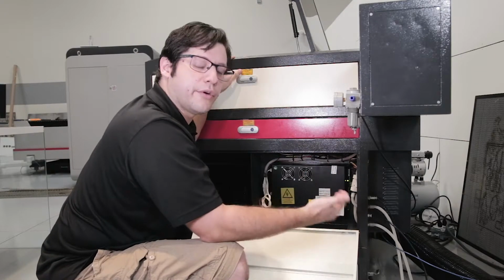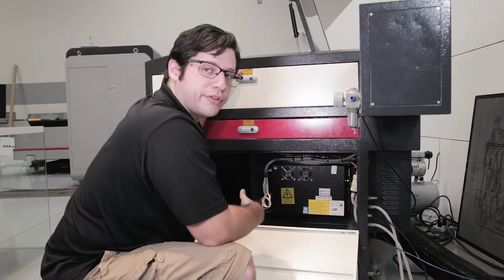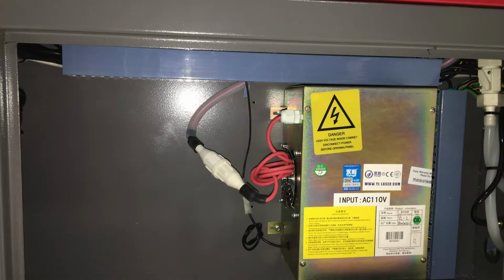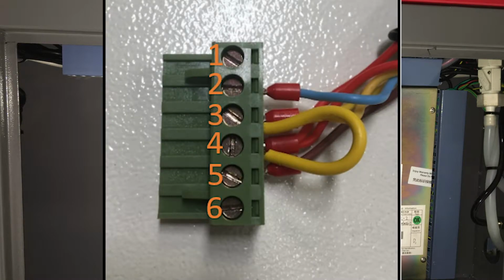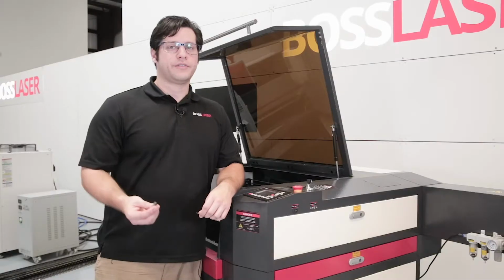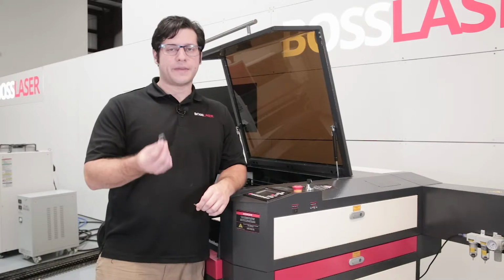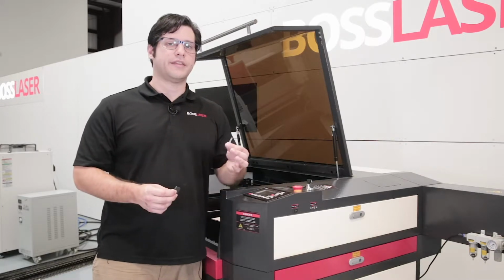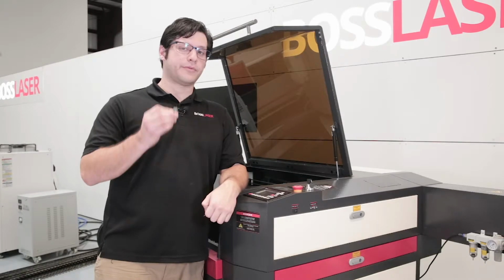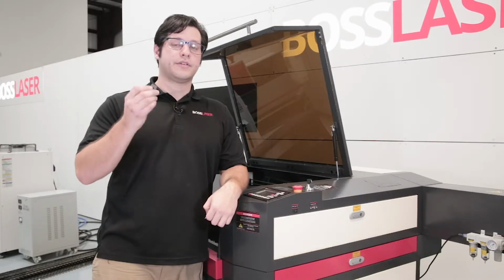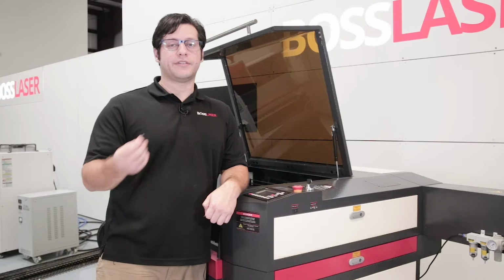So from here, we're going to go ahead and go to our door interlock and check that. If you have a gold power supply, you may need to loop your 3 and 4 using the cable that comes on the 6-pin. So you would unscrew that and place it on 3 and 4, and then go ahead and pulse it on your control panels. So checking the door interlocks, you're going to need 2 items. One is a magnet that doesn't come in your toolbox, and then the pin. The magnet we're going to use, we're going to go ahead and place on top of the interlock to see if it will fire.